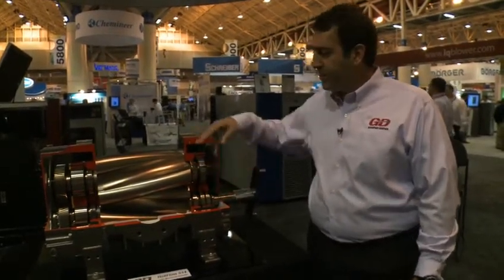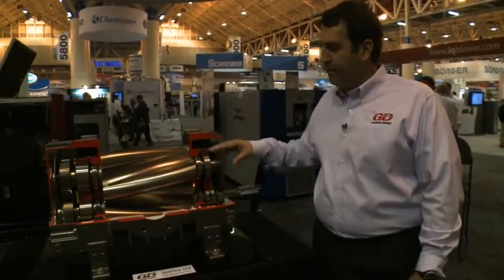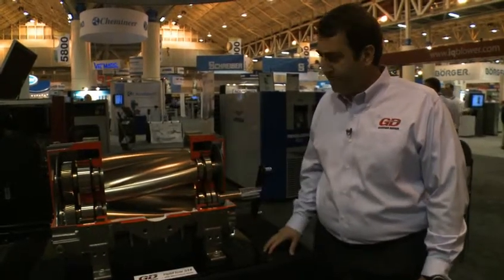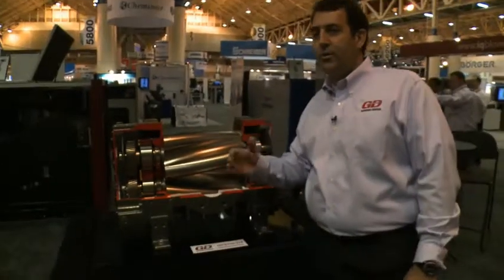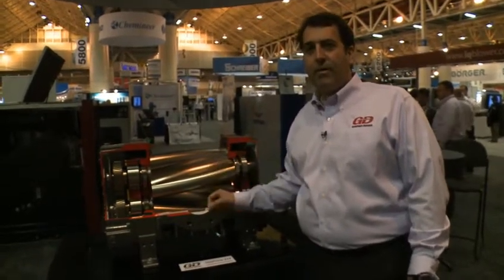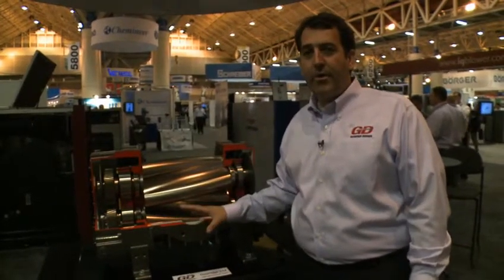It is a one-piece ductile iron rotor and shaft assembly, so you don't have to worry about any product buildup in the lobes causing unbalance. As you can see also, it has a plenum on the discharge, and that helps reduce the noise even more when the air comes across the discharge into your pipe. It helps to feed back some air and cut down more vibration and noise. This particular machine is between 5 to 7 dBA quieter than a standard traditional PD blower.